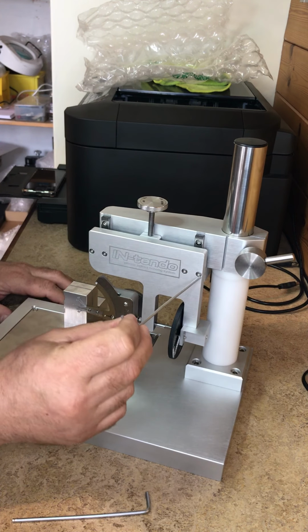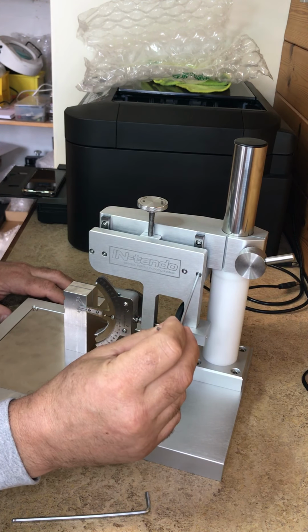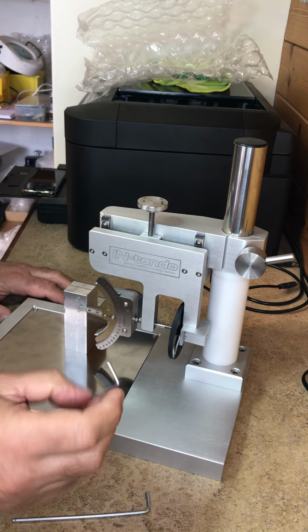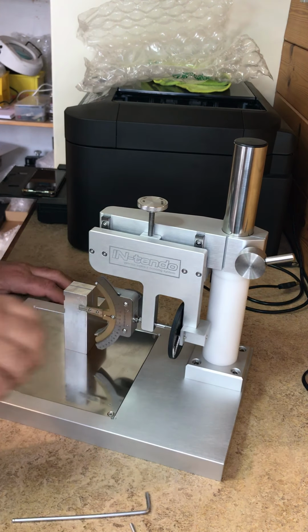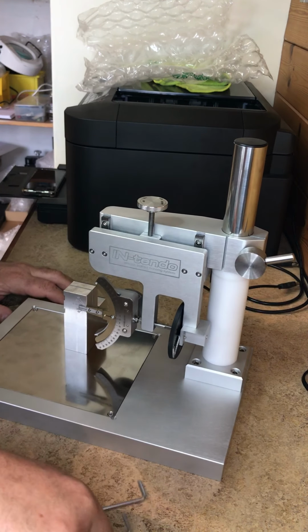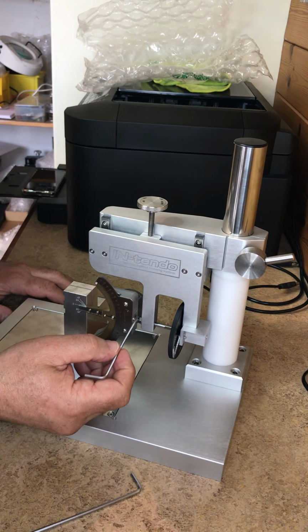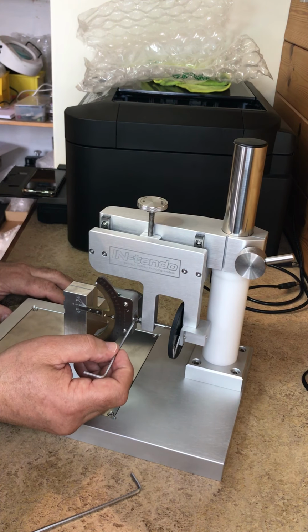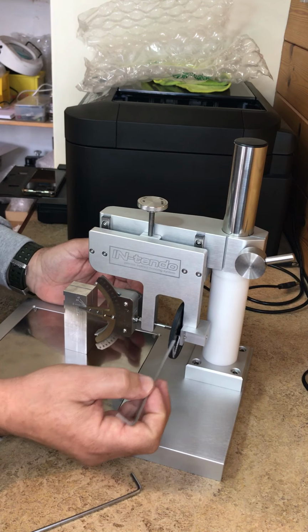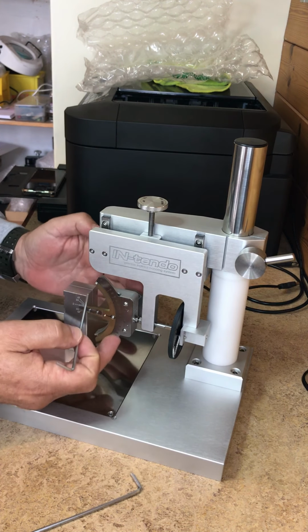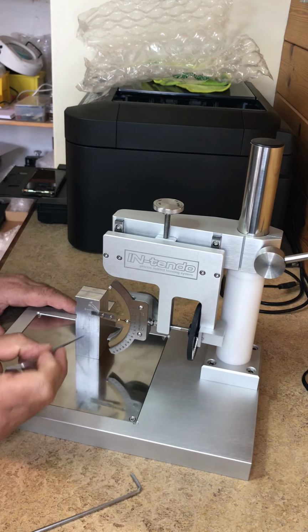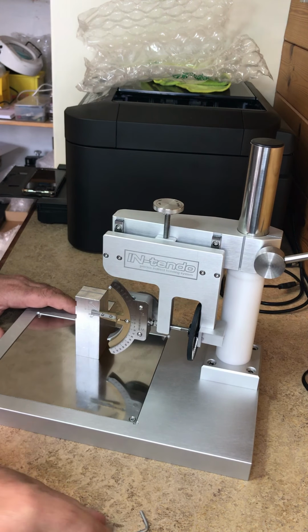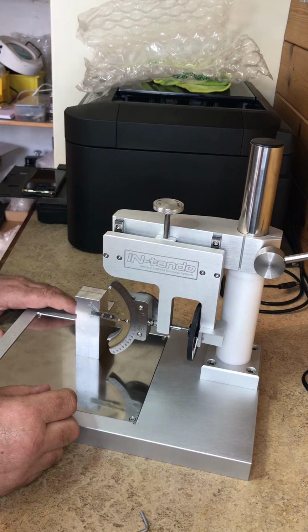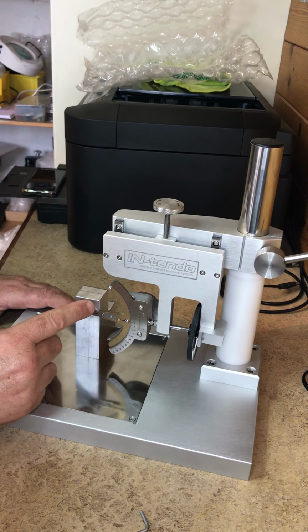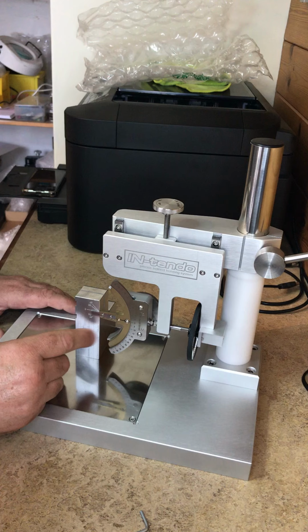The same thing, just another sized Allen key that fits in there. And the other possible area is this nut here, the locking nuts for the head. So if you did need to adjust, you would loosen the locking nuts, check that the tip is 0, check that the torque is 0, and then you can adjust using the calibration jig. The calibration jig has two different ways of being used. You can either use it with the scribe marks here. So this is set at 0 now.